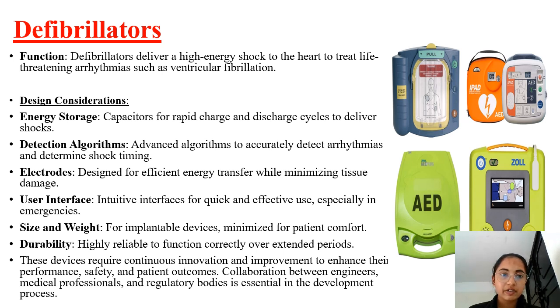So next is defibrillation. This is the function. Defibrillators deliver a high energy shock to the heart to treat life-threatening arrhythmias such as ventricular fibrillation. Next is the design of this. Energy storage: capacitors for rapid charge and discharge cycles to deliver shocks.